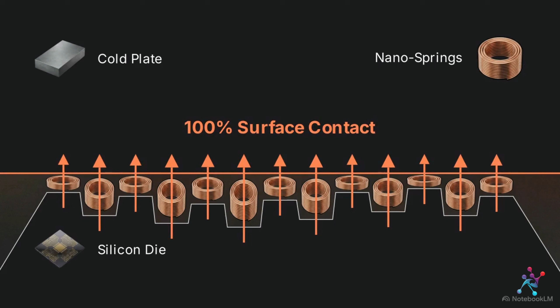The material's structure relies on vertical nanosprings, copper nanowires aligned into direct thermal pathways. Under physical pressure, these springs act as a compressible gasket. They compress to guarantee 100% surface contact with the silicon die, eliminating the microscopic air gaps that trap heat. This architecture achieves a thermal conductivity exceeding 1,500 watts per meter Kelvin, nearly 4 times the efficiency of legacy copper, without a single moving part.